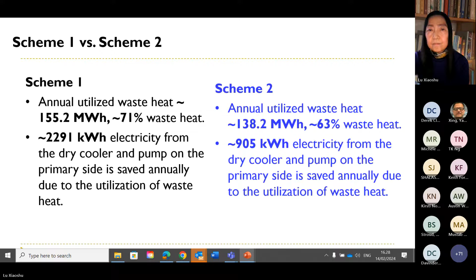We also developed a new relationship graph based on the two schemes, because a linear correlation can be found among the waste heat reuse rate, outdoor temperature, as well as space heating supply temperature. Therefore, this graph can be used to aid in designing the heat recovery system, or HX2. And there are some new discoveries that can be found from the graph.